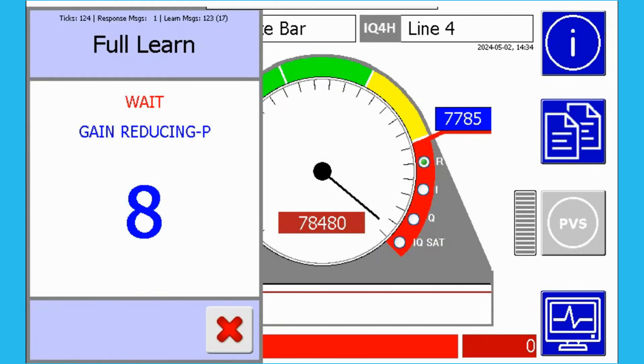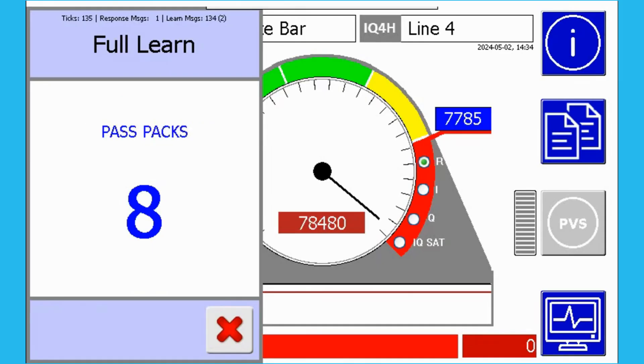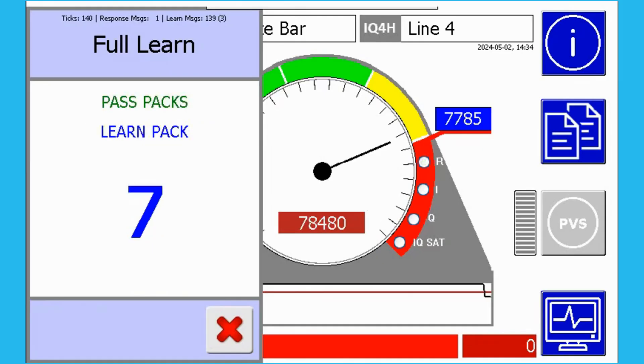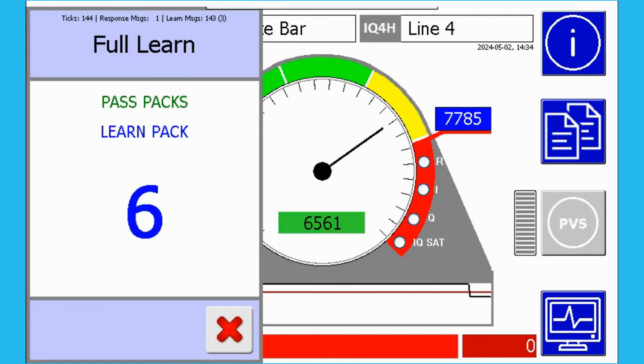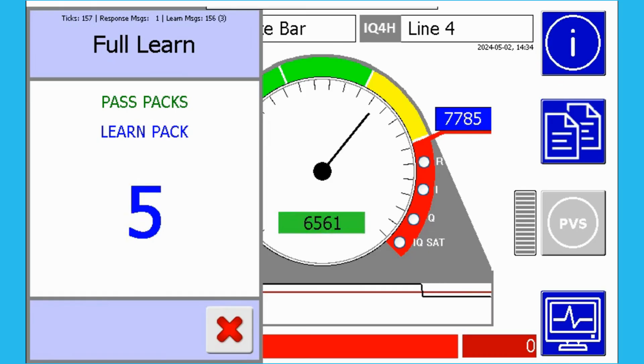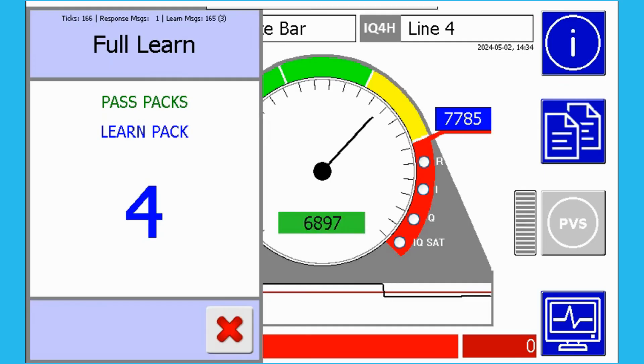When the full learn message box displays a wait message, you should wait before passing the next pack to allow the metal detector signals to reset. The counter will reset when settings are adjusted internally, so you will need to watch the full learn message box to know when to pass a pack and when to wait, to allow the head to settle before passing the next pack.